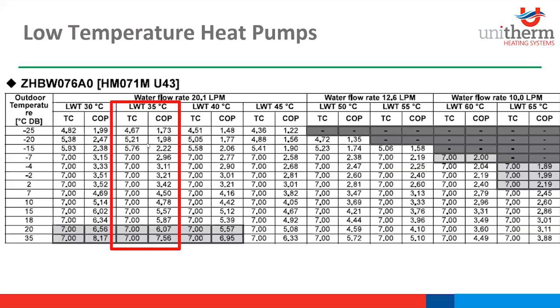Just a quick look at some capacity tables. As I mentioned, you have 100% performance down to -7. So -7 degrees here on the left is our outdoor temperature. TC up here is total capacity. Now that's total capacity without a backup heater, whereas the majority of heat pumps will show total capacity, but that will be including a backup heater.